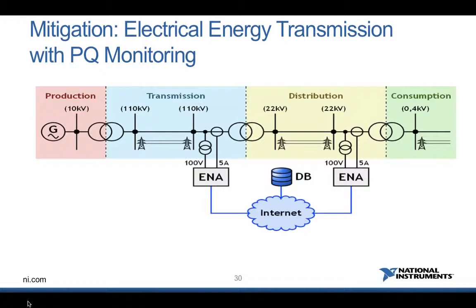Similarly to how Roberto was talking about PMUs, the situation is similar with power quality analyzers. To really get a good picture of what's happening in the grid, it's not sufficient to measure at just one point. Typically we should have multiple analyzers doing continuous measurement, calculating parameters, and sending data across, for instance, the internet, to a power quality database server that stores data from multiple analyzers. Then we should have a software application doing analysis of the data coming from several sites.